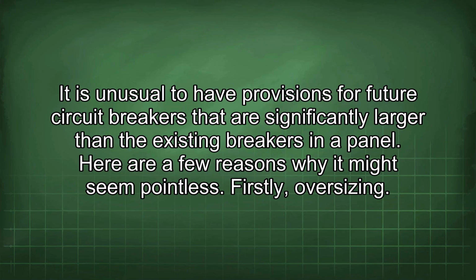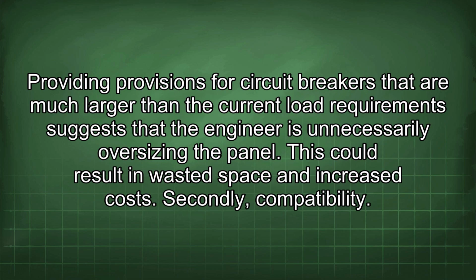It is unusual to have provisions for future circuit breakers that are significantly larger than the existing breakers in a panel. Here are a few reasons why it might seem pointless. Firstly, oversizing. Providing provisions for circuit breakers that are much larger than the current load requirements suggests that the engineer is unnecessarily oversizing the panel. This could result in wasted space and increased costs.